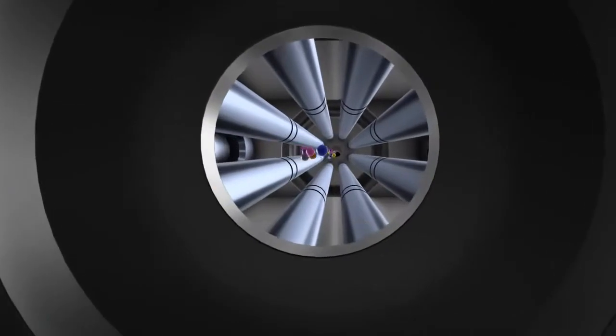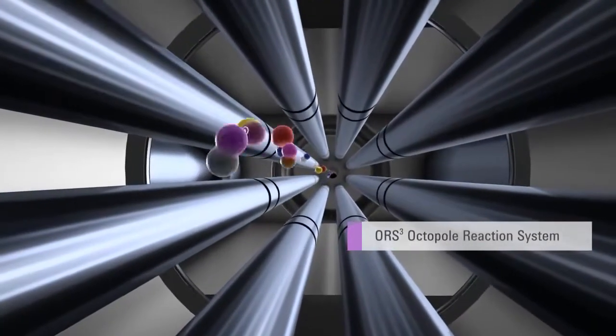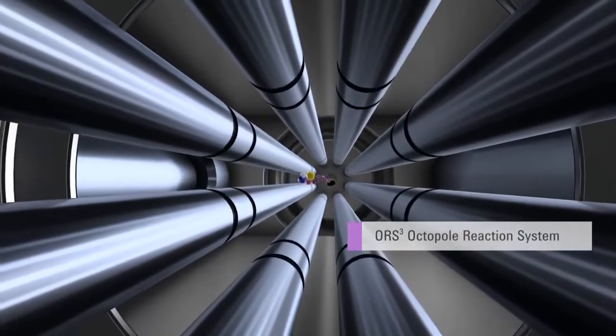All 7700 series instruments include Agilent's renowned collision reaction cell, the third generation ORS-3. For most industries and sample types, the ORS-3 uses helium collision mode, and polyatomic interferences are removed using Kinetic Energy Discrimination, or KED.